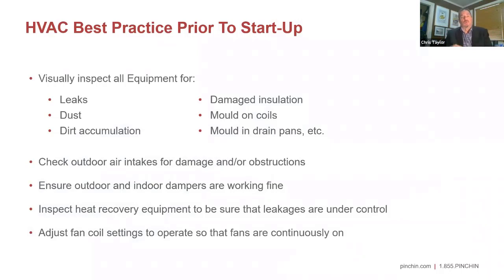So inspect, go through and do that hard inspection on any of your wet systems, certainly looking for evidence of biofilms, looking for evidence of mold, looking for obstructions, things like louvers. If they haven't been looked at in a while, are they either locked open or locked shut? We've had situations where even on computer controlled systems, the computer control says the louvers are open, but when you visually inspect them, the louvers are in a closed position because they're stuck. So going through and really doing an eyes-on inspection of your entire system, almost like a startup phase, like if you were commissioning the building, is absolutely going to be valuable as you get yourself back to full occupancy.